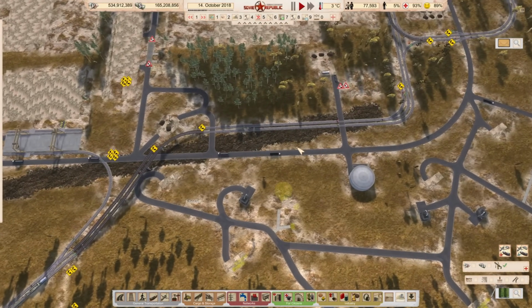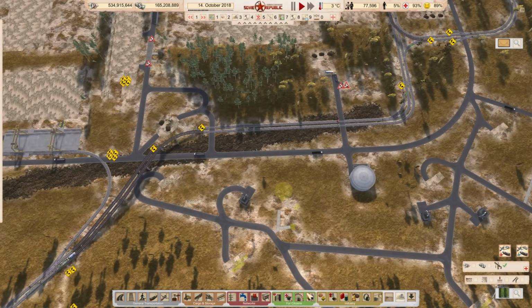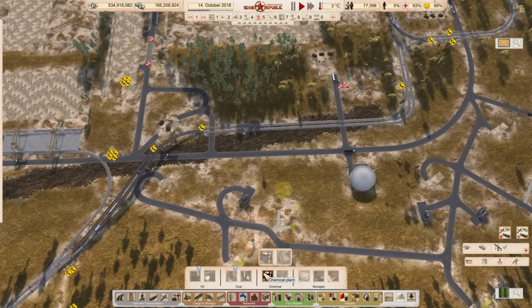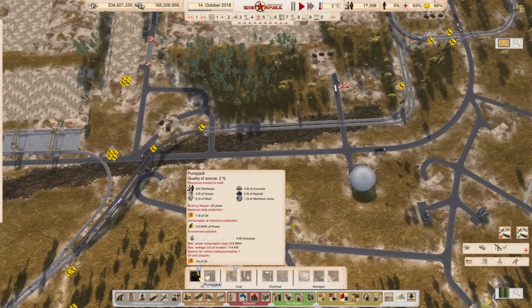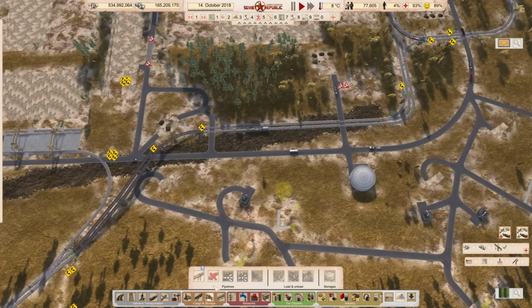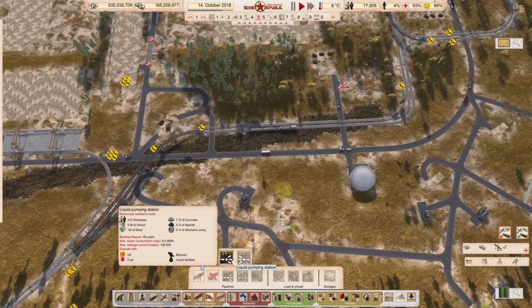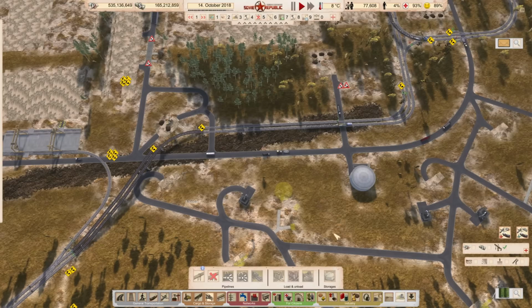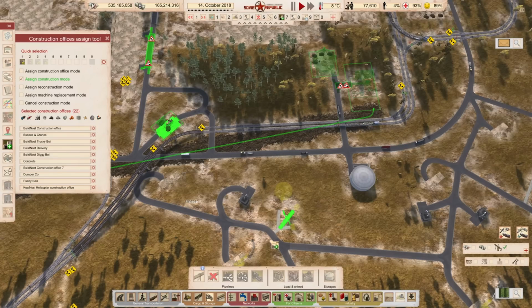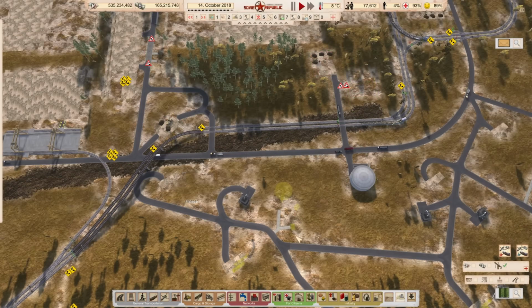Alright, so I need to do some calculations when it comes to power. So fossil fuels, we have oil pumps, the pump jacks. Looking at the circuit breaker, it's 114 kilowatts each. That's the base number I need for every single pump jack. On top of that I also have pumps, and I have an awful lot of pump jacks, needing 149, so we'll go with a ballpark rough number of say 150.